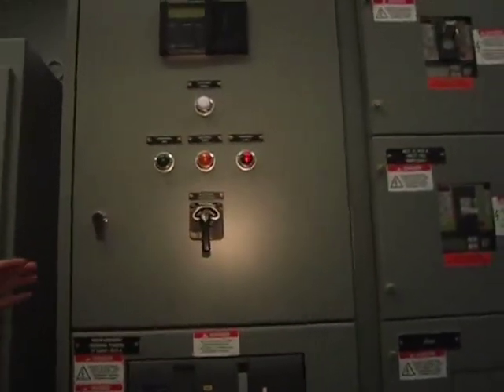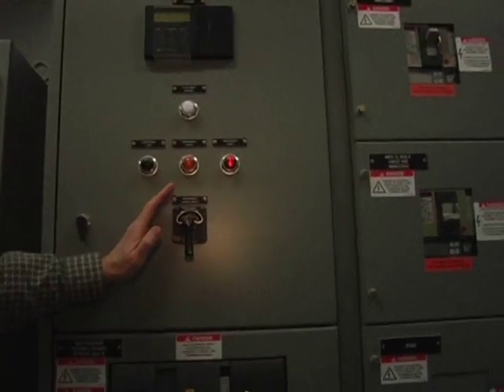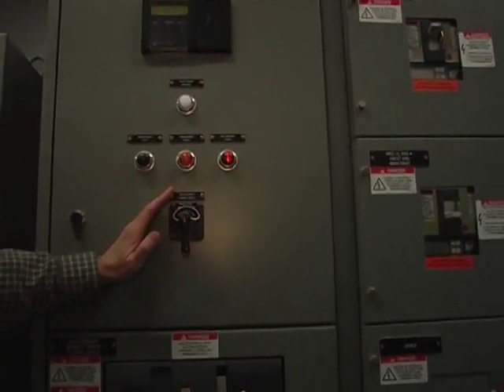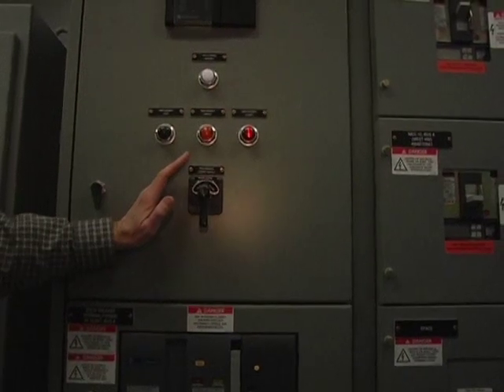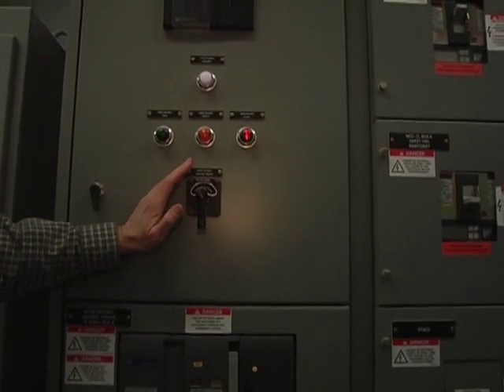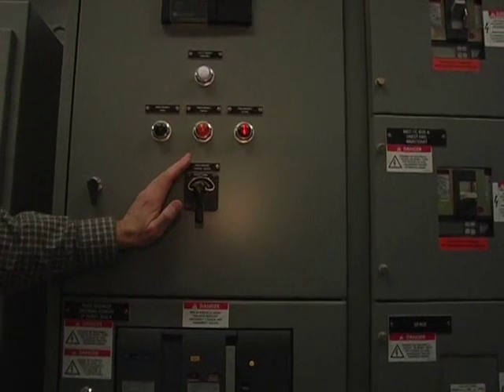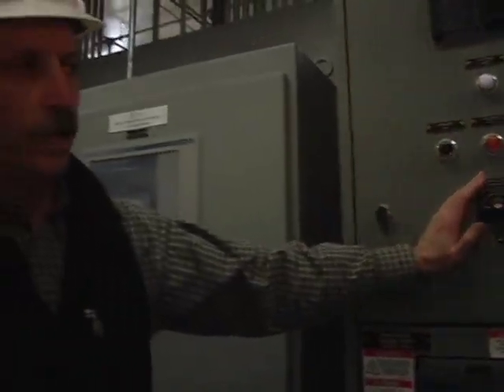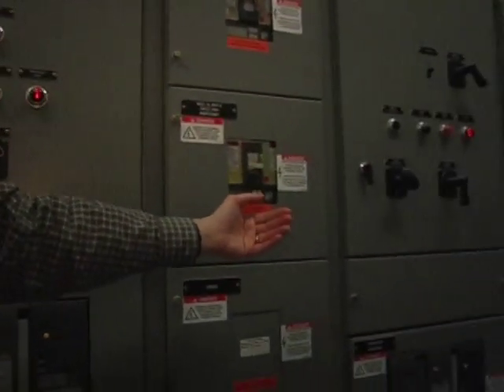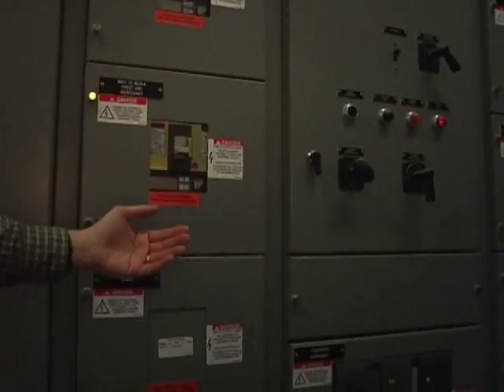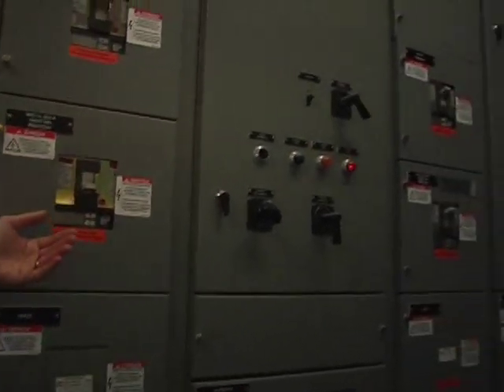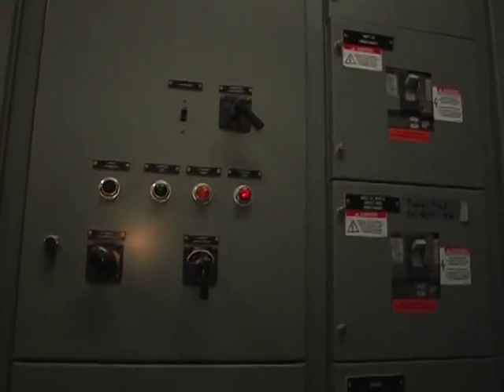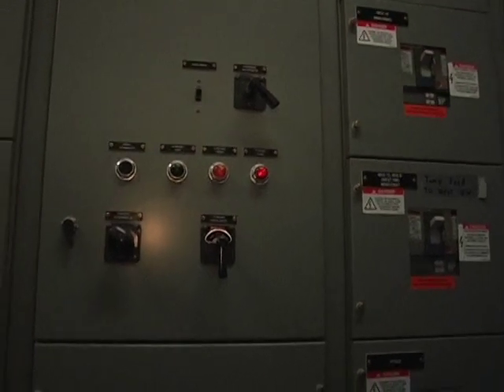Over to my right here is the automatic transfer switchgear, which again is sensing the power supply coming in through the main utility. If in fact this equipment senses a power loss, namely a power outage in the area from the utility system, then the transfer gear will send a signal to the generator to start the generator. Once the generator is up and running and up to speed, then the transfer gear will switch the load from the utility breaker over to the generator breaker and put the process back online.